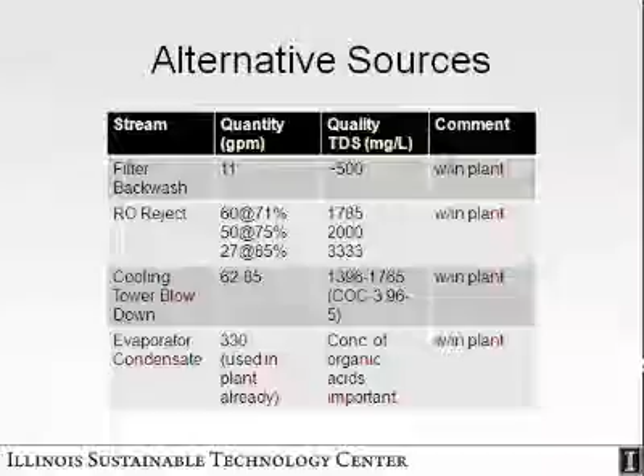So just to give an example of how you might substitute for the process water using an alternative water source, we'll take the cooling tower blowdown, which is about 85 GPM, and match it with the process need, which is about 75 GPM. So the question is: since I have cooling tower blowdown roughly the same quantity required in process, can I take that blowdown water and actually use it for process purposes?